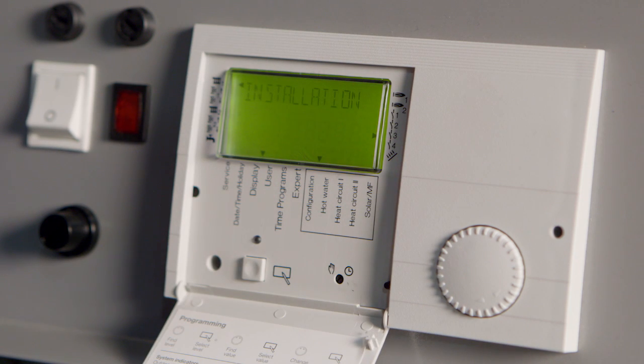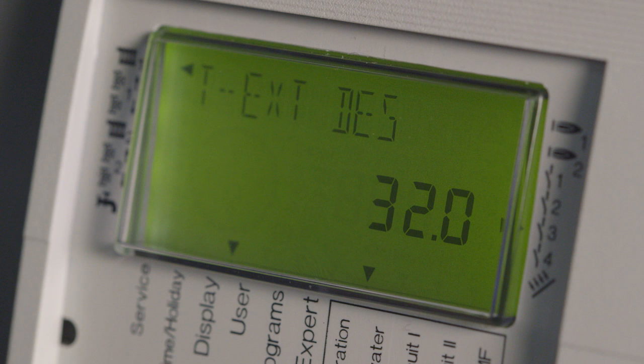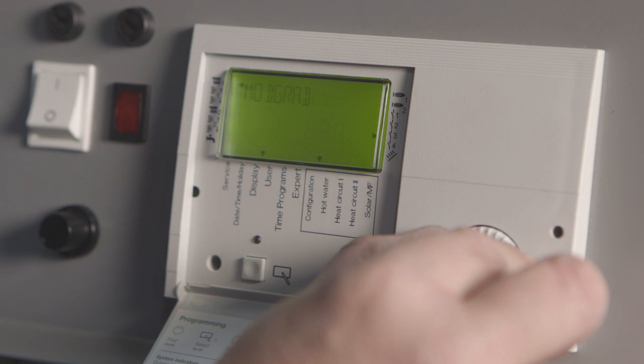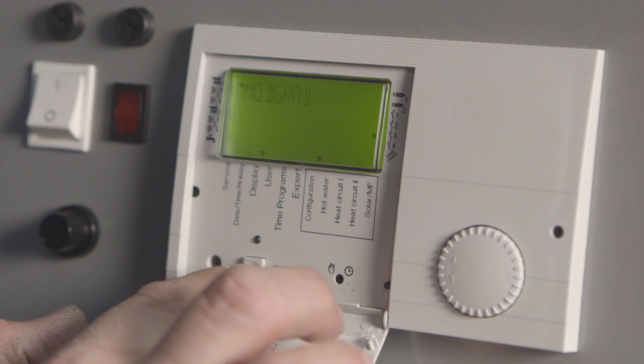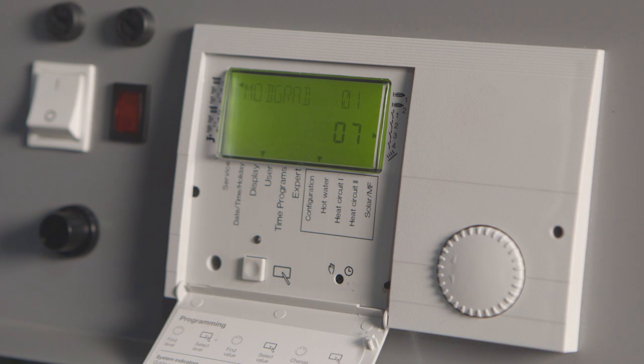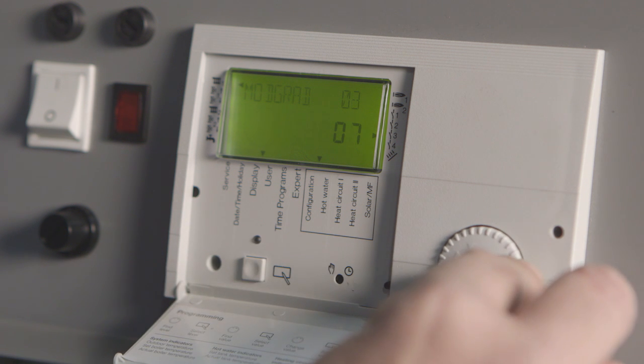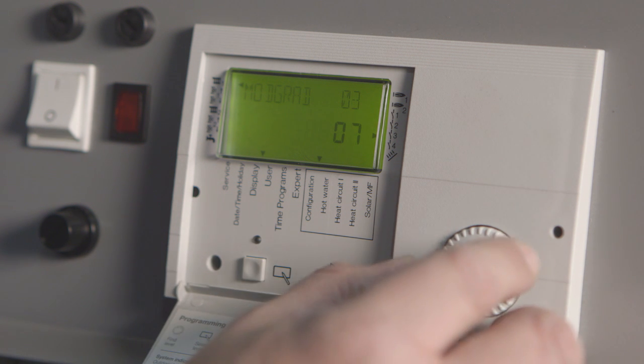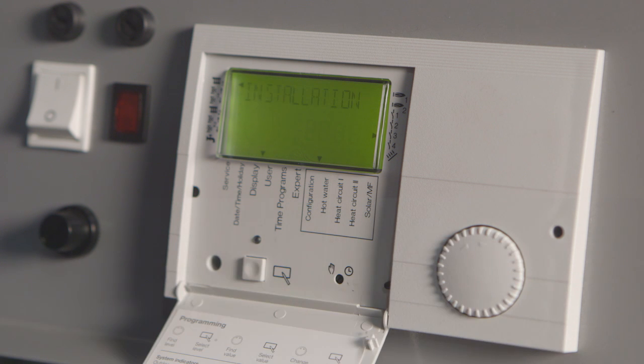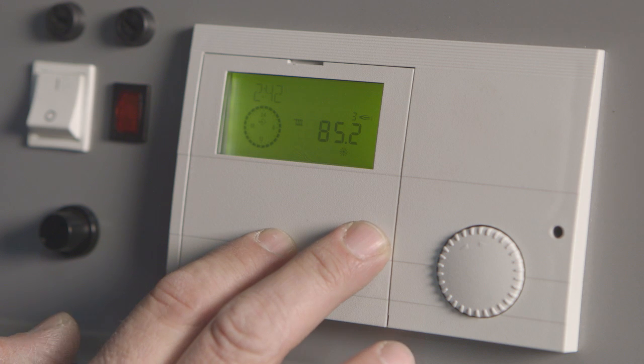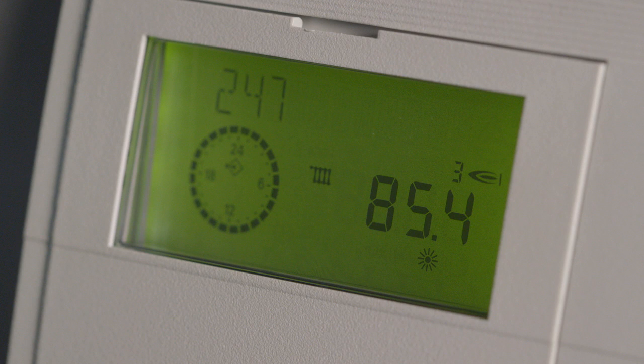Open the E8 panel door. The installation menu will appear. Scroll the wheel until you reach T external DES, which is your unit's remote set point. Continue scrolling until you reach ModGrad. Hit this button. Now you can view the individual burners, turning the wheel to view each one individually as shown. When you're finished, scroll to return. Hit the button one more time to return to installation. Close the E8 door. On your display screen, you can view the number of units firing here.